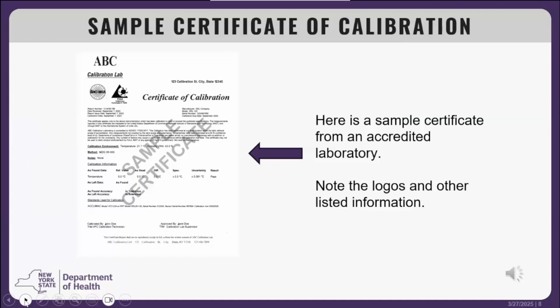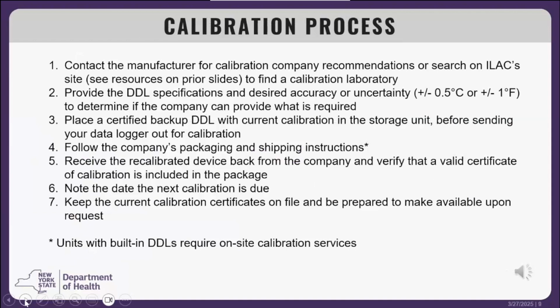The DDL manufacturer should be able to provide information on recommendations for recalibration of your data logger. They will need to know the accuracy or uncertainty requirements within plus or minus 1 degree Fahrenheit or plus or minus 0.5 degrees Celsius. Before sending your data logger out for calibration, you must place a certified calibrated backup data logger in your vaccine storage unit, as the storage units must be constantly monitored. When the data logger is returned, look for the calibration certificate in the box. If not included, immediately contact the company and request it to be emailed or faxed. Calibration certificates must be made available upon request from the New York State VFC program. Also note that units with built-in digital data loggers require on-site calibration services.